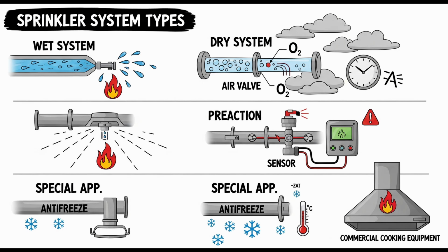Quick opening devices, QODs, are also required at the dry pipe valves in these combined systems. Yes. Given the potentially large system size and the critical need for rapid water delivery once detection occurs in these potentially large and hazardous pier or terminal environments, QODs are mandated to accelerate the trip time of the main dry valves. Get water moving fast.